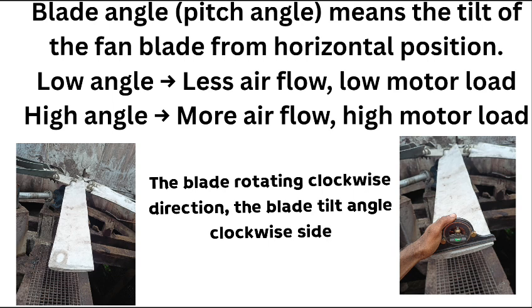The blade angle means the tilt of the fan blade from the horizontal position. A low angle means less airflow and low motor load. A high angle means more airflow and high motor load. The blade rotates in the clockwise direction. The blade tilt angle is on the clockwise side.